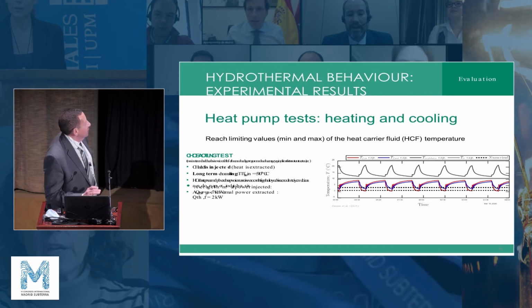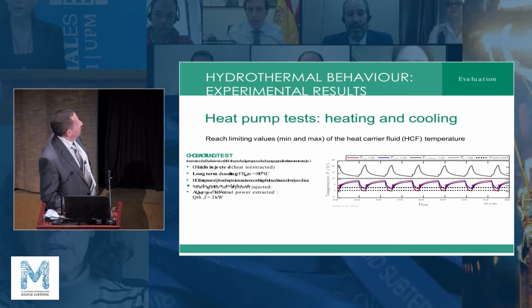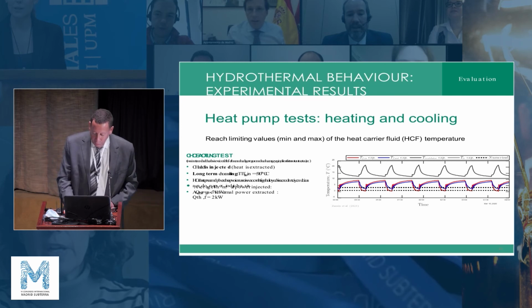And the cooling test, where we extract heat and inject cold, we limit it to 0 degrees Celsius, the temperature we inject in the ground, which is rather conservative, I would say. In this case, we got an average thermal power extracted of 2 kilowatts.